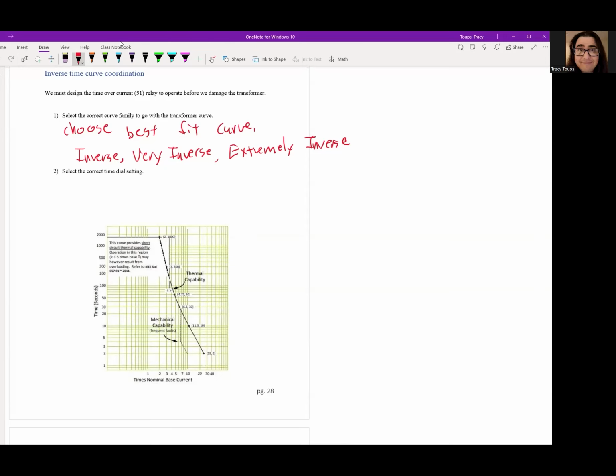Okay, once we pick that, select the correct time dial. Remember, the time dial will move the curve to fit the transformer damage curve. We'll say move the, and let's put right here relay curve, just to make sure we differentiate the difference, the relay curve. So for example, here, let's see if I'm a good artist today. We will have, oh, that's way too wide. We shouldn't be using that. The curve should be something like, that might be a little too small.